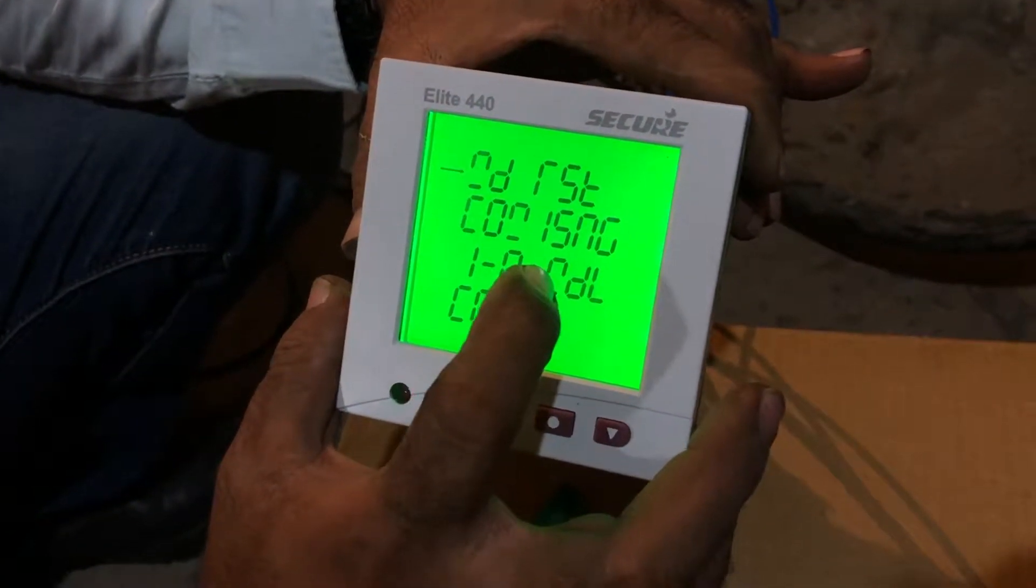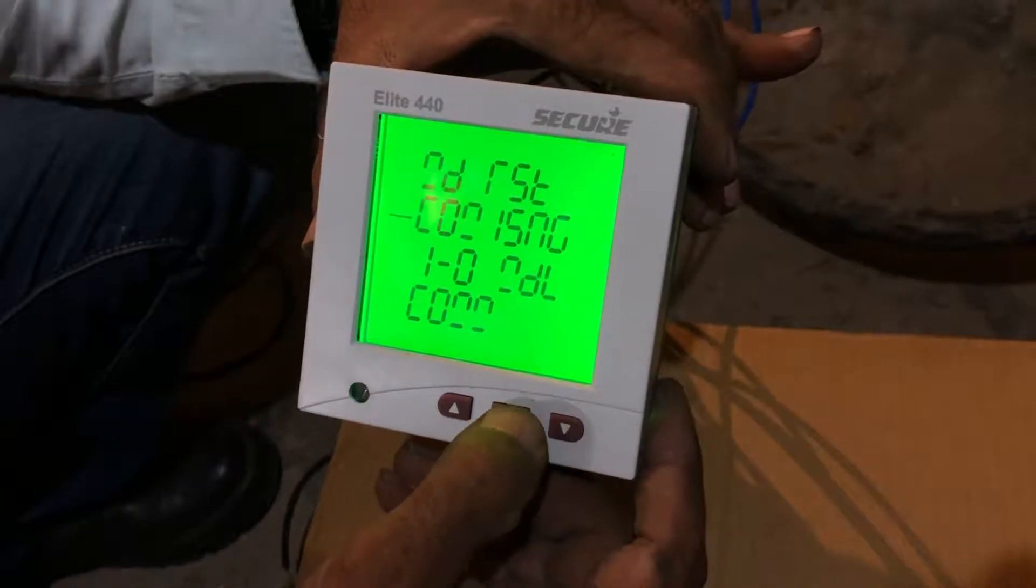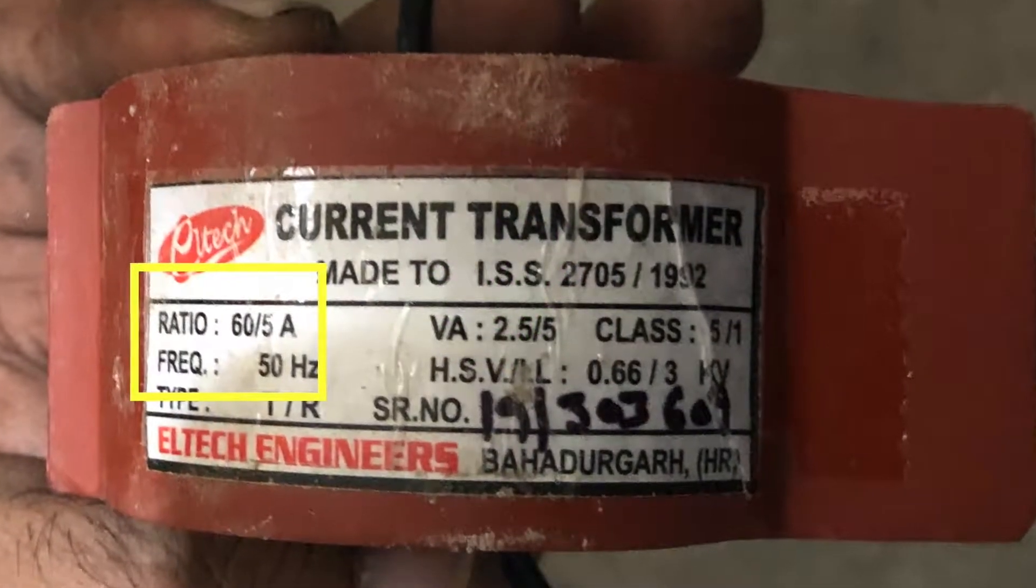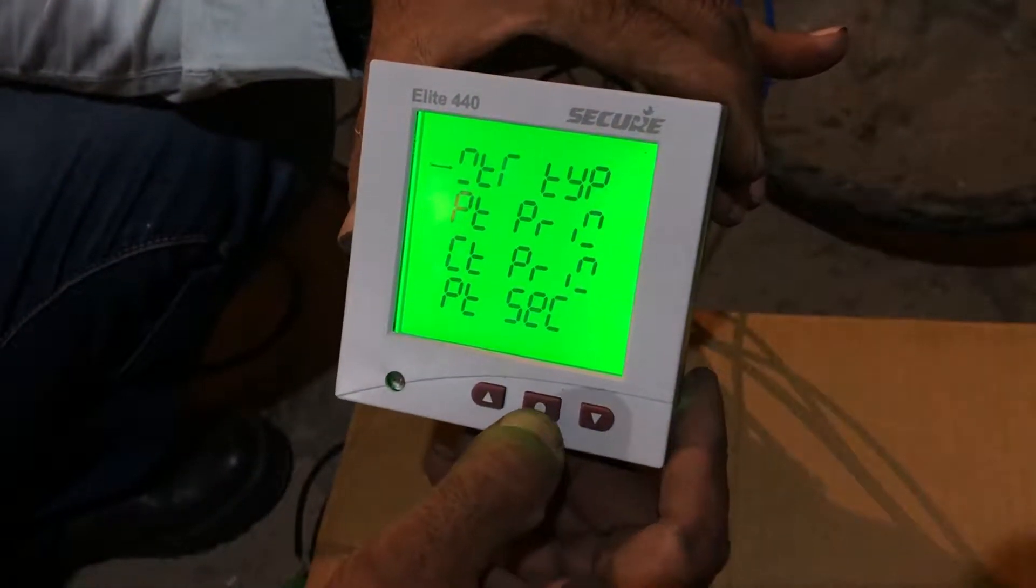This menu says commissioning. As seen on the CT, the ratio is 60 is to 5. We will put the same on our MFM.